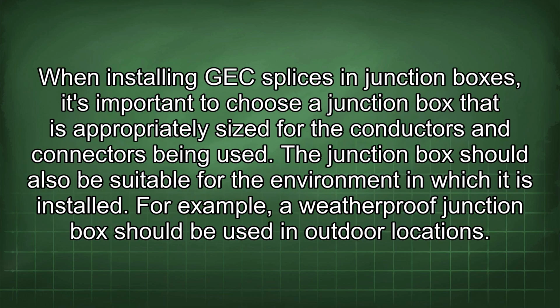When installing GEC splices in junction boxes, it's important to choose a junction box that is appropriately sized for the conductors and connectors being used. The junction box should also be suitable for the environment in which it is installed. For example, a weatherproof junction box should be used in outdoor locations.